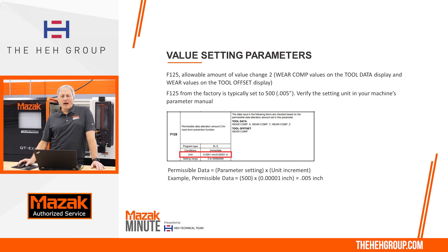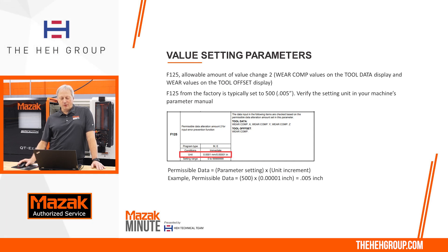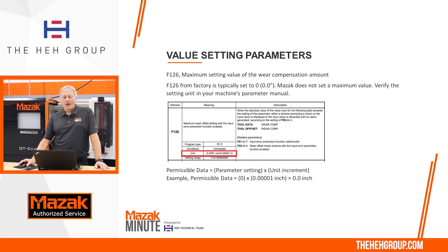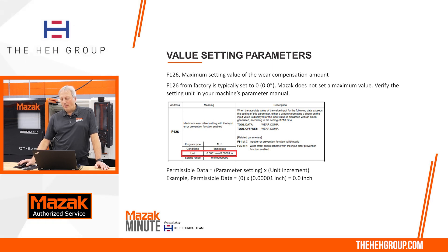Now let's look at F125, which Mazak calls value change 2. This monitors the wear comps on the tool data or the wear comps on the tool offset screen. Mazak typically sets this to 500, which is the equivalent of five thousandths. The F126 parameter is the maximum setting of the wear compensation amount, and the factory setting is zero.